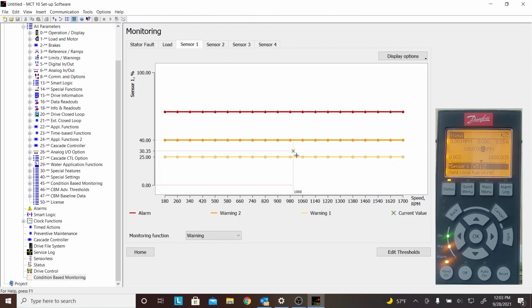We're in warning 1, we're over the yellow. Sensor 1, which is our vibration sensor, says, hey, we have a WS12, we have our first warning. That means we're starting to degrade. Now it gives us time. This is really early in the process here. It gives us time now to react to that, order parts, figure out what our maintenance plan is going to be on that.